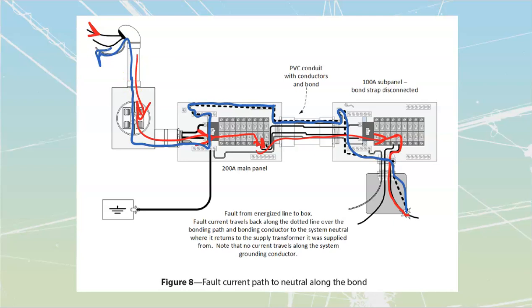Current forms complete loops, right? It's going to have to return back to the transformer. That's where it wants to go. And we see in this case, absolutely nothing is flowing up the actual grounding conductor itself, the one over there. This one over here, we see that under faults, it carries nothing. That's why we're getting away with a number 6. We'll talk about that a little bit later on.